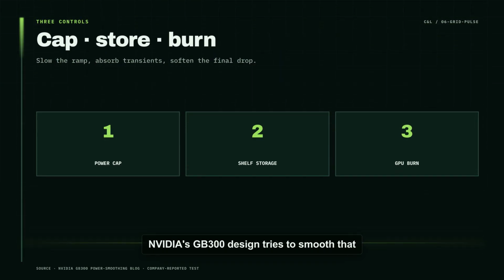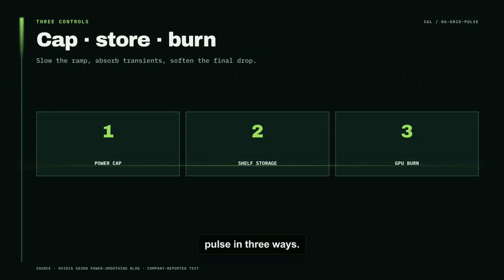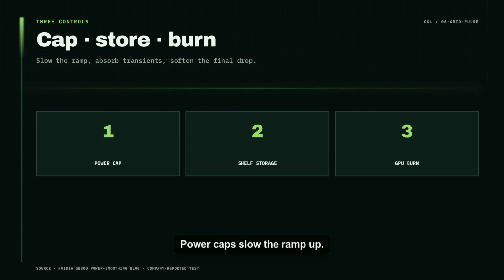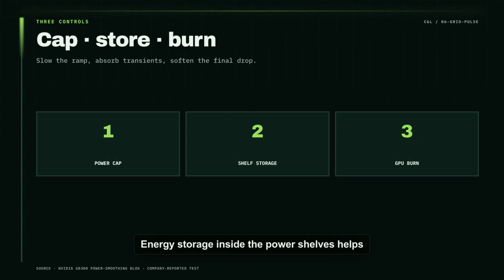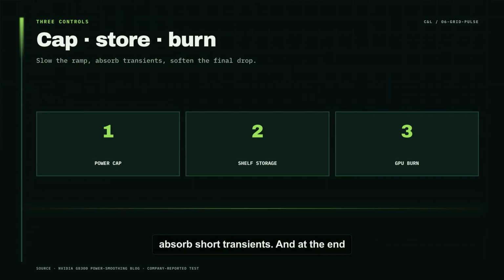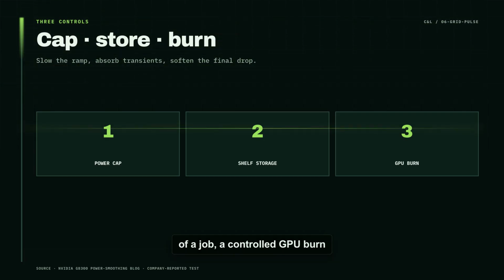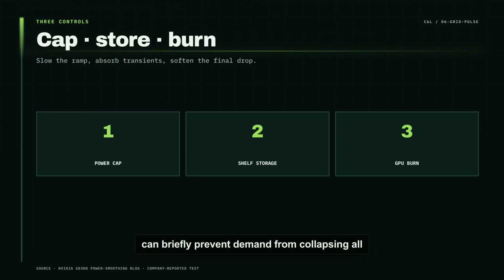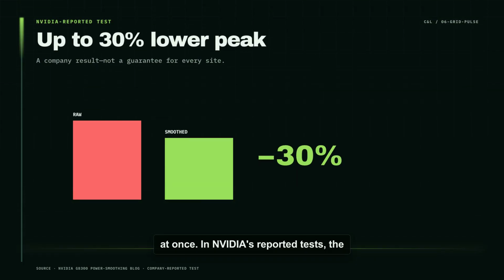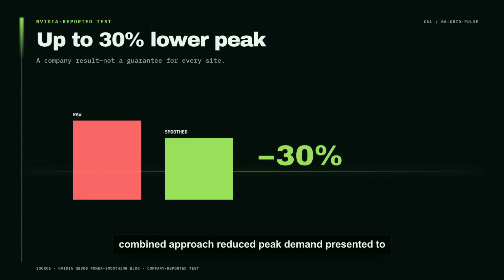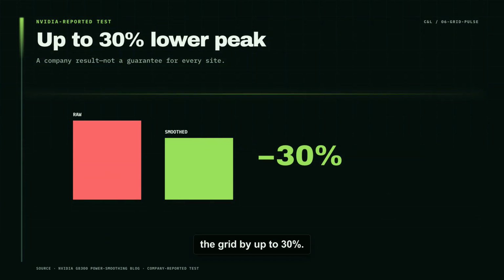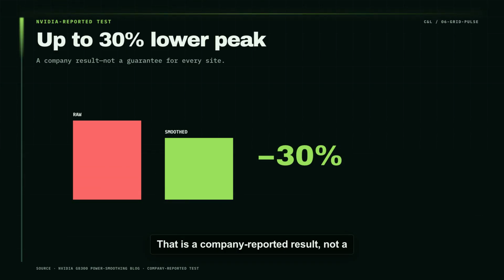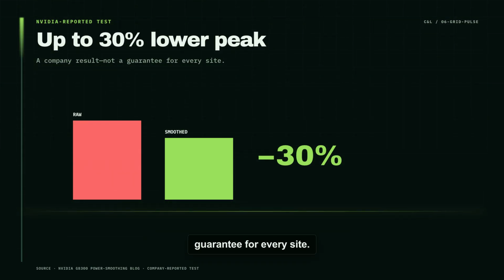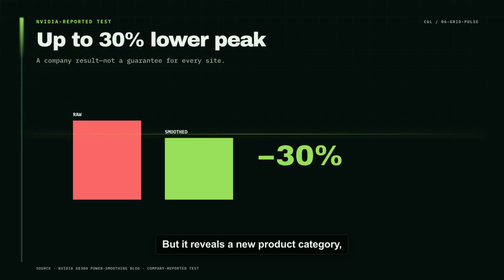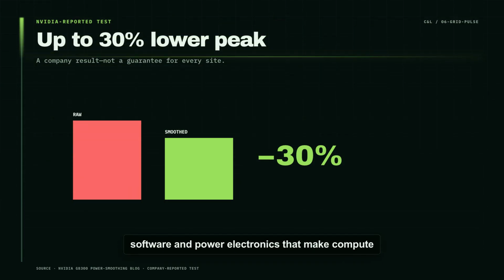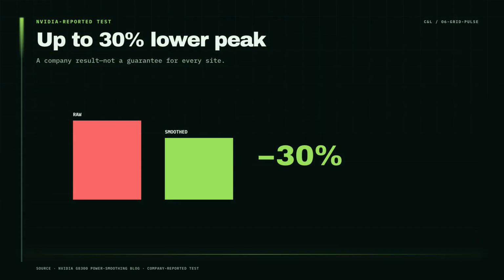NVIDIA's GB300 design tries to smooth that pulse in 3 ways. Power caps slow the ramp up. Energy storage inside the power shelves helps absorb short transients. And at the end of a job, a controlled GPU burn can briefly prevent demand from collapsing all at once. In NVIDIA's reported tests, the combined approach reduced peak demand presented to the grid by up to 30%. That is a company-reported result, not a guarantee for every site. But it reveals a new product category, software and power electronics that make compute look calmer to the grid.